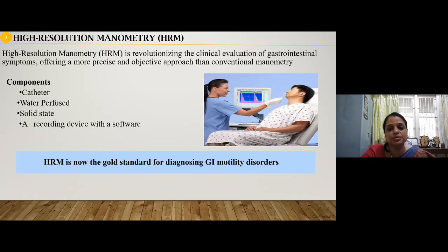In terms of instrument setup, the manometry system includes a catheter that detects the intraluminal pressure at multiple points along the gastrointestinal tract. There are two types of catheter. In the previous slide I showed the solid state catheter, which has inbuilt miniature pressure sensors, and the water perfused catheter, which is connected to external pressure transducers and continuously perfused with water. High resolution manometry catheters typically contain more sensors, 20 to 36 sensors, which are closely spaced for detailed pressure mapping. Along with the catheter, the system has a recording device with software. The computer or monitor displays real-time pressure data in the form of color-coded topographic plots, along with software that supports calibration, real-time monitoring, data recording and analysis.